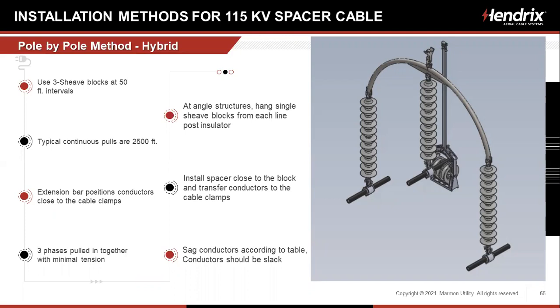We're going to have continuous pulls up to 2,500 feet, depending on the conductor size. If it's a smaller conductor, we would do more than that. We're going to have extension bar position conductors close to the cable clamps, as you can see here. 3 phases are going to be pulled together with minimal tension. At angle structures, we're going to hang single sheave blocks from each line post insulator. And we're going to install the spacer close to the block and transfer the conductors to the cable clamps.